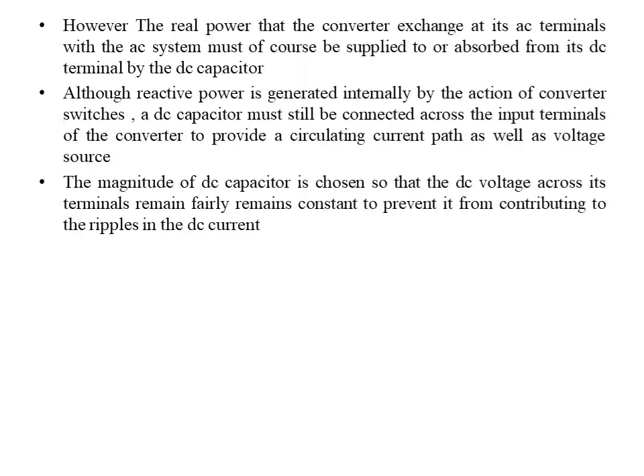In practice, the semiconductor switches of the converter are not lossless, so the energy stored in the DC capacitor is used to meet the internal losses of the converter, and the DC capacitor voltage diminishes. However, when the STATCOM is used for reactive power generation, the converter itself can keep the capacitor charged to the required level. This task is accomplished by making the output voltage of the converter lag behind the AC system voltage by a small angle. In this way, the converter absorbs a small amount of real power from the AC system to meet the internal losses and keep the capacitor voltage at the desired level.